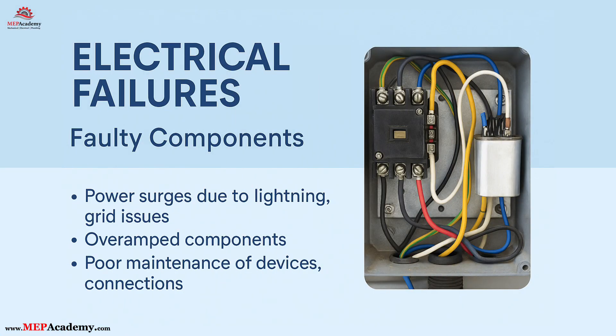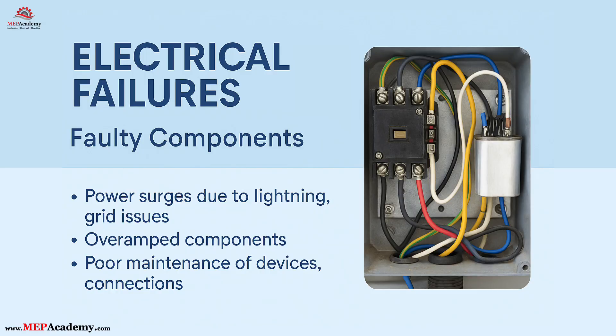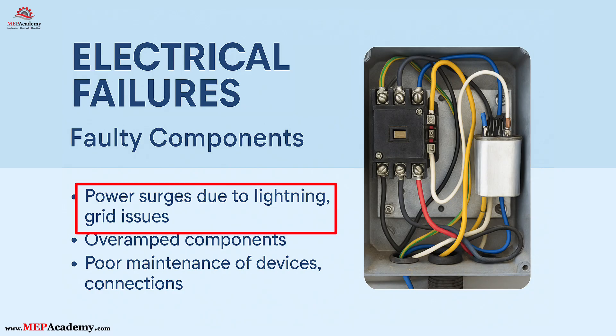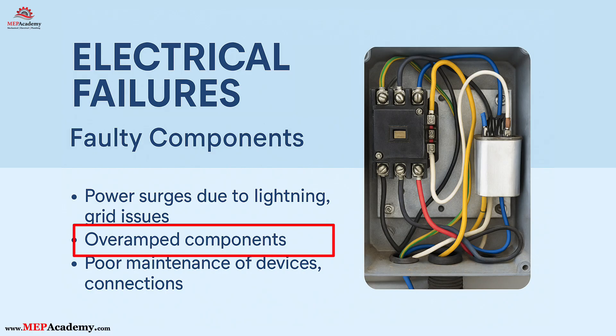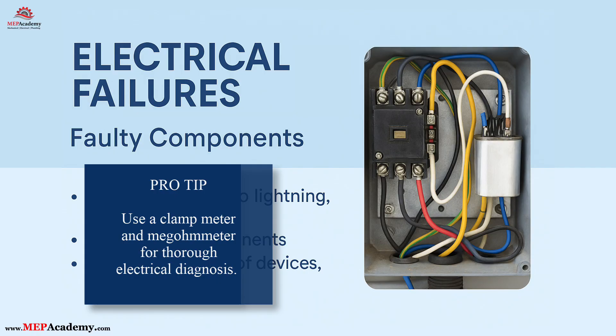Number six: electrical failures — faulty components. From bad contactors to failed capacitors and sensors, electrical failures can take down an otherwise healthy refrigeration system. Always inspect for loose terminals and degraded wiring. Common causes: power surges from lightning strikes, utility grid switching, or large equipment cycling; over-amped components when motors draw more current than designed due to mechanical binding, low voltage, or internal faults; and poor maintenance allowing dust, corrosion, loose connections, or worn components to cause overheating, arcing, and eventual breakdown. Pro tip: use a clamp meter and megohmmeter for thorough electrical diagnosis.